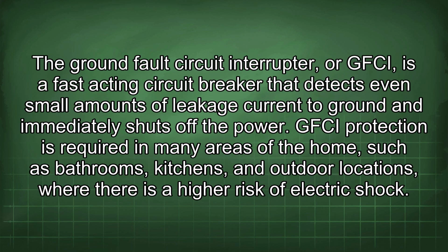The ground fault circuit interrupter, or GFCI, is a fast-acting circuit breaker that detects even small amounts of leakage current to ground and immediately shuts off the power. GFCI protection is required in many areas of the home, such as bathrooms, kitchens, and outdoor locations, where there is a higher risk of electric shock.